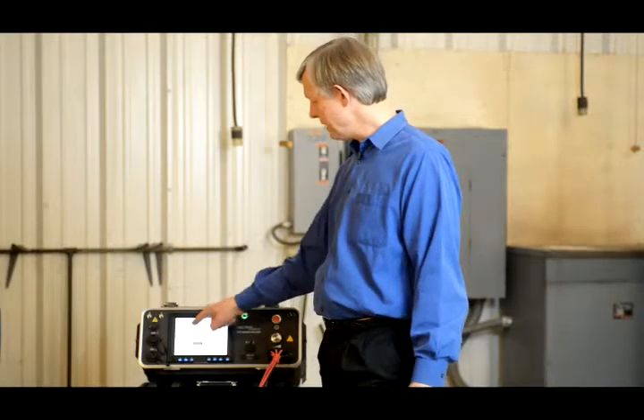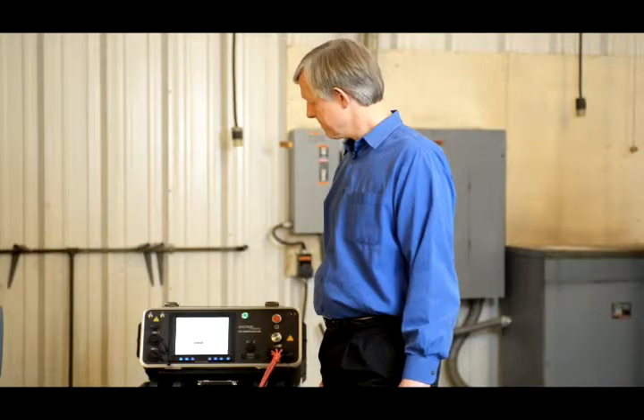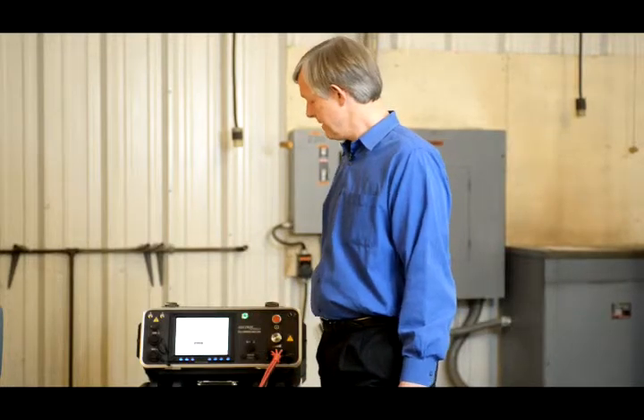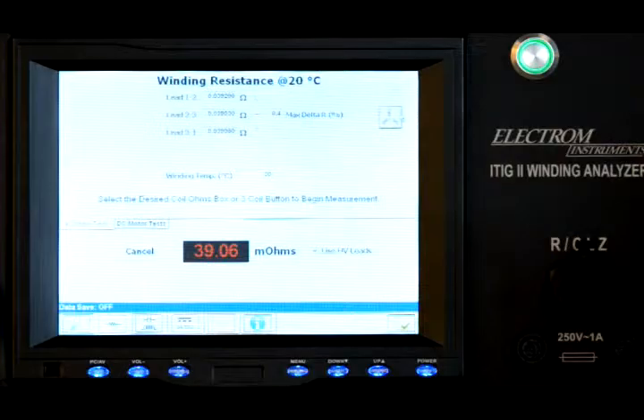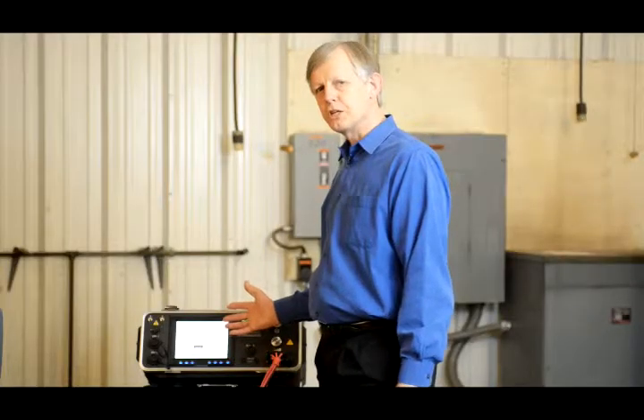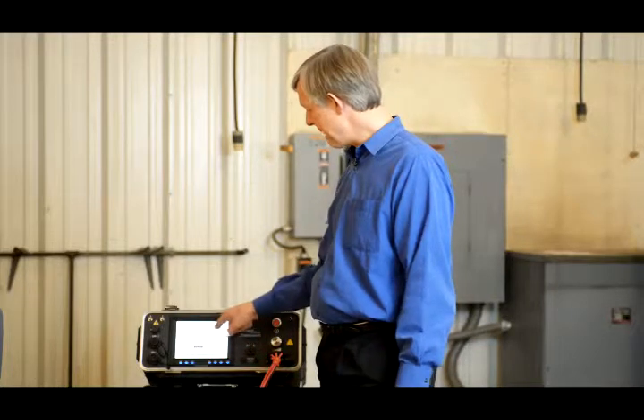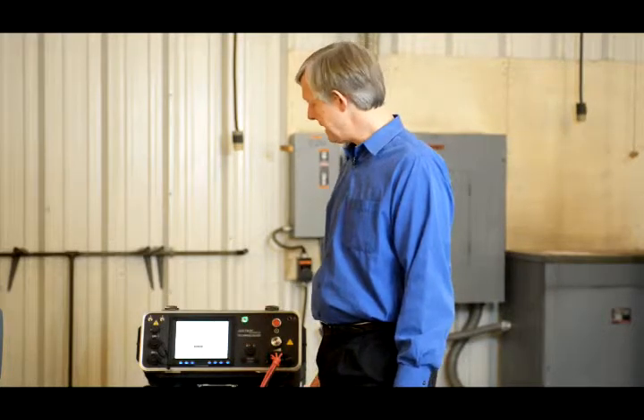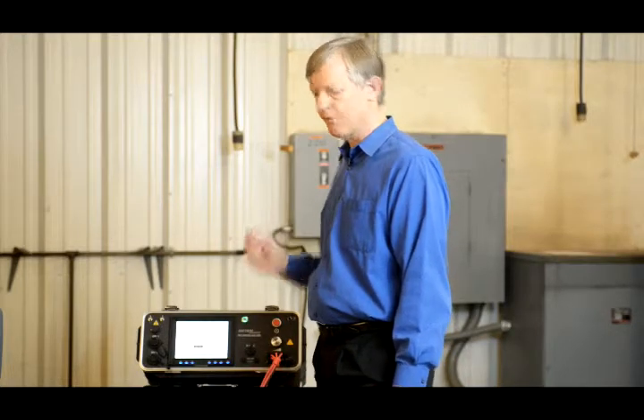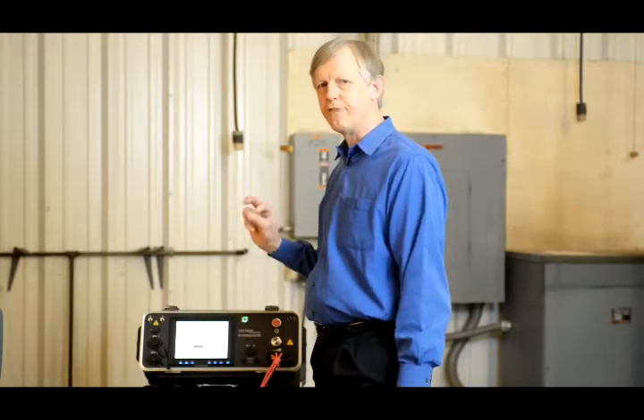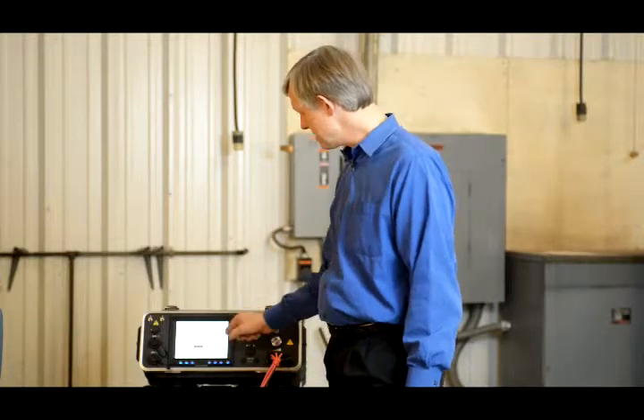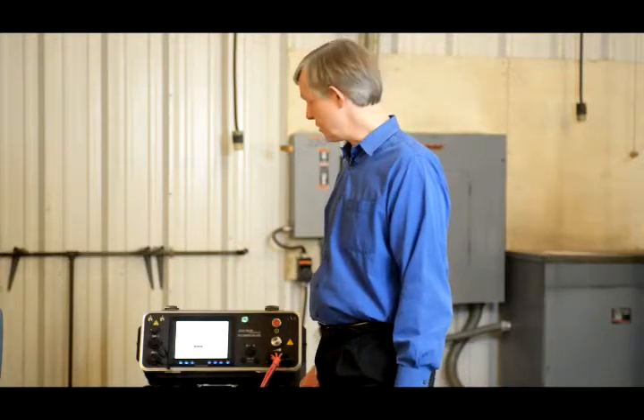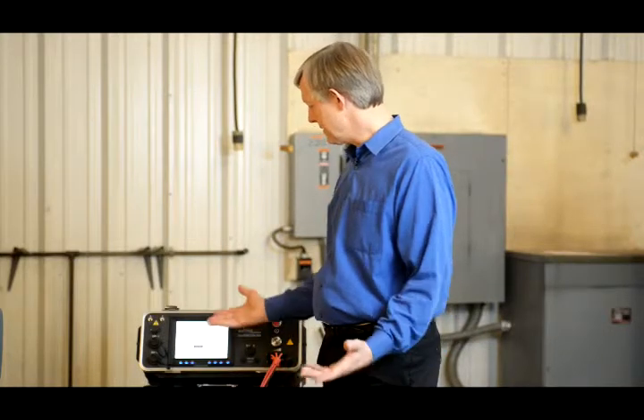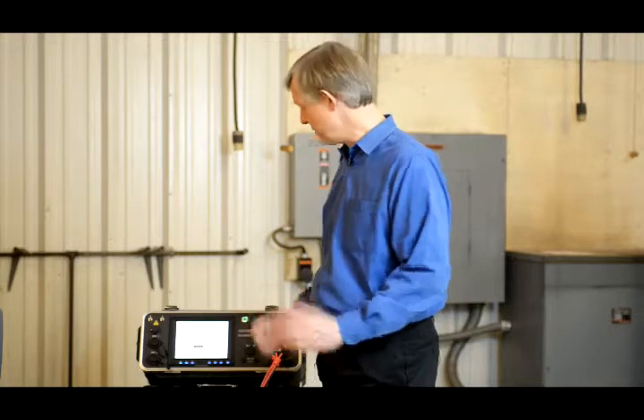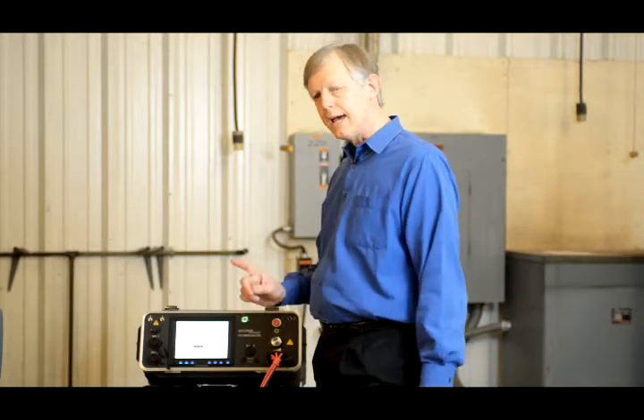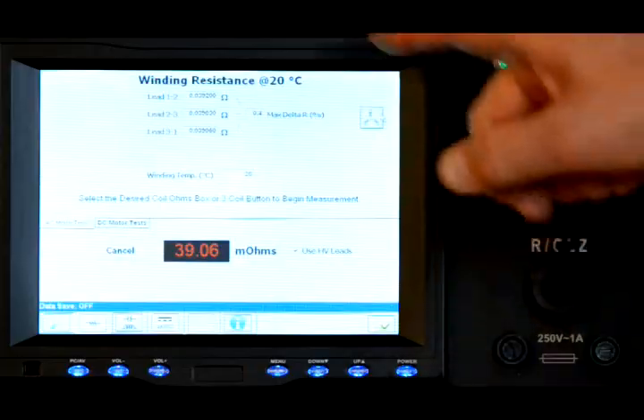So it moved automatically now to lead 2 and 3. Takes a little while to stabilize again before it moves to lead 3 and 1. Once all 3 measurements are done, it will calculate the max delta R %. That is the maximum distance of one of these 3 measurements from the average of the 3 measurements. And in this case, it's 0.7%, which is a good result, and it's a good motor as far as winding resistance is concerned. In this case, this measurement was done at 20 degrees C.